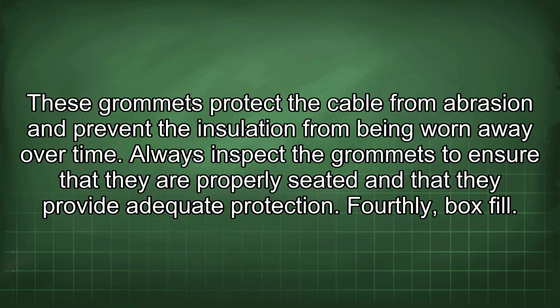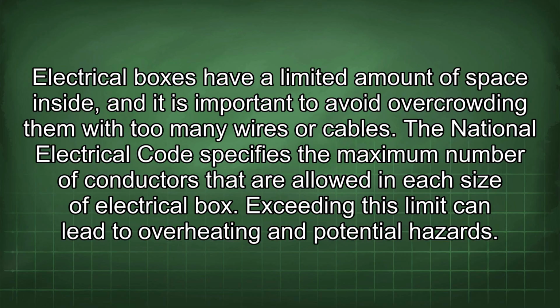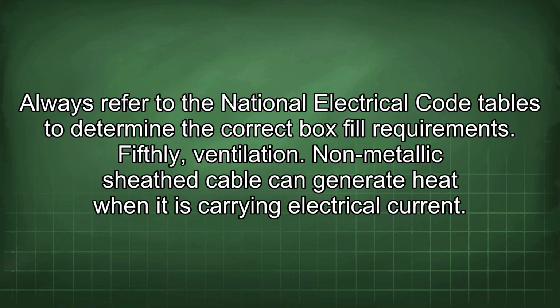Fourthly, box fill. Electrical boxes have a limited amount of space inside, and it is important to avoid overcrowding them with too many wires or cables. The National Electrical Code specifies the maximum number of conductors that are allowed in each size of electrical box. Exceeding this limit can lead to overheating and potential hazards. Always refer to the National Electrical Code tables to determine the correct box fill requirements.